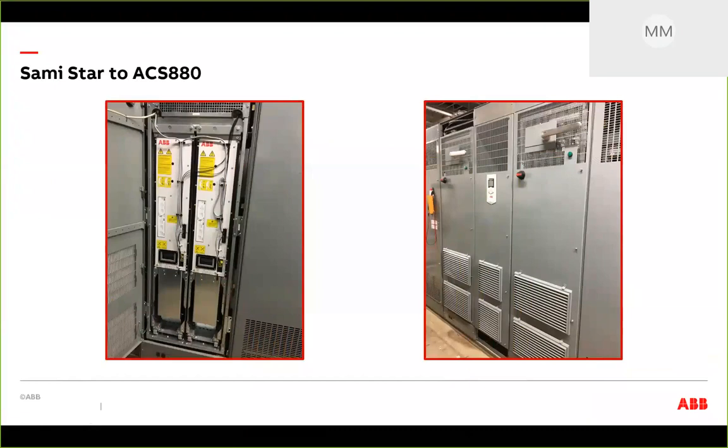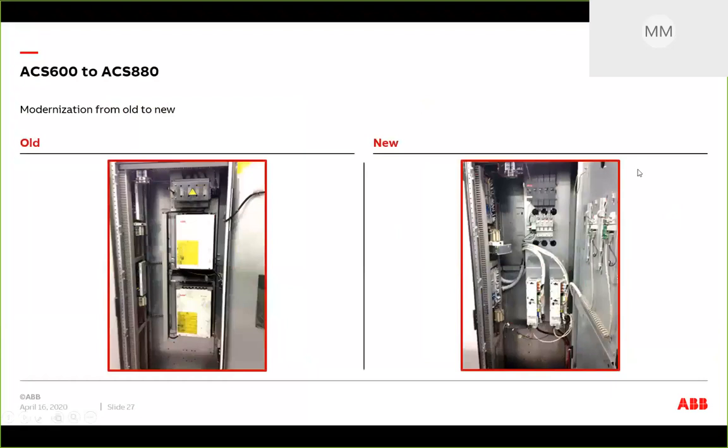On the right there, you can see those were actually new doors, made to cleanly fit the installation and have the HMI on the door and those large metal handles at the top. That was all pre-ordered and set up to pull a very old drive section out of there and retrofit it in during an extended outage. Which is what you're showing here, going from some of the older technology to the newer technology.